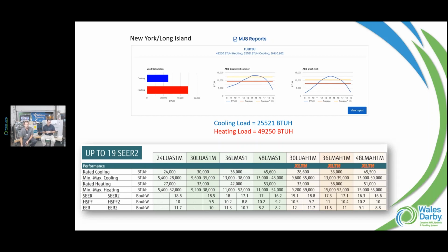So now we just grossly oversize, CYA it, we don't want complaints - and then here comes the summer and all of a sudden we can't get rid of the humidity. That's what Jeff's saying right now, and that's 100% - that's where that rebate... we're hearing a lot in the Northeast and all over, I'm guessing, about rebate dollars that are out there trying to put everybody on a heat pump. And that's great, if we're doing the sizing and we understand what the machine can do. So hopefully after today you'll have a better understanding of what we're talking about.